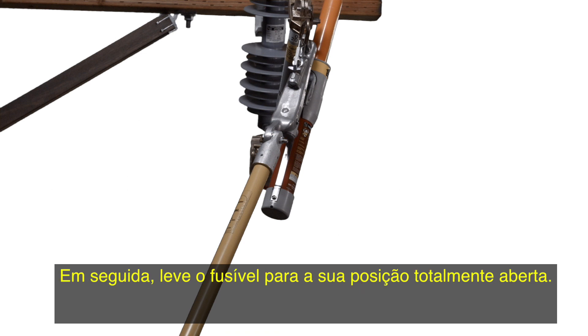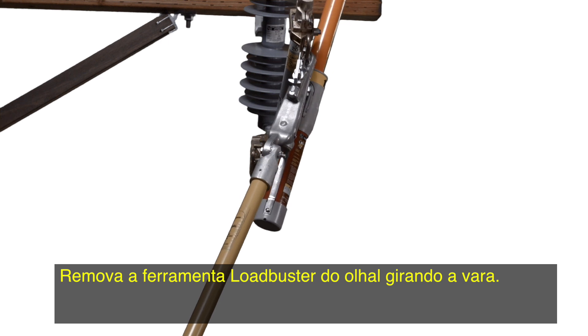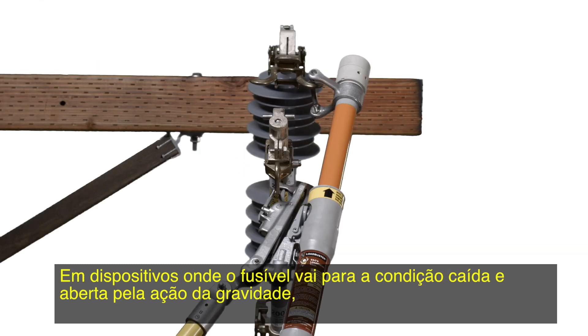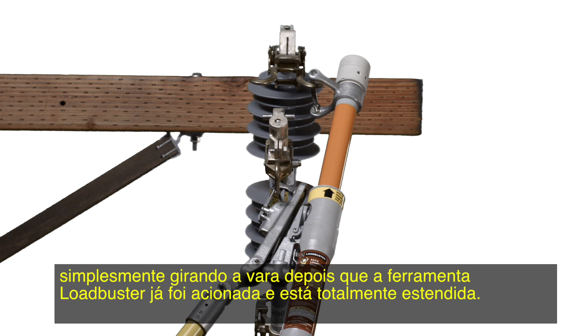Next, bring the fuse toward its fully open position. Remove the Loadbuster tool from the pull ring by turning the pole. This will deflect the pull ring latch to release the pull ring. On devices where the fuse will drop fully open by gravity, it may be preferred to remove the Loadbuster tool by rolling it off both the attachment hook and pull ring at the same time, merely by twisting the pole after the Loadbuster tool has been tripped and fully extended.